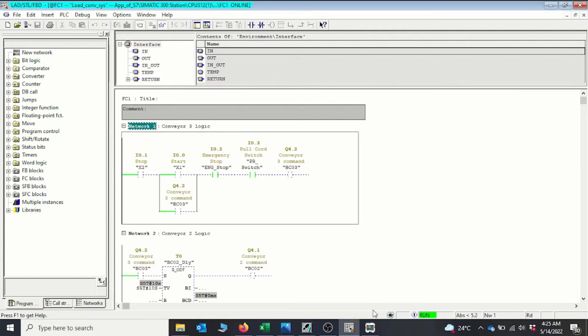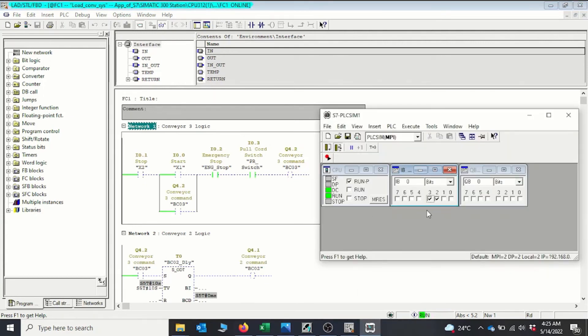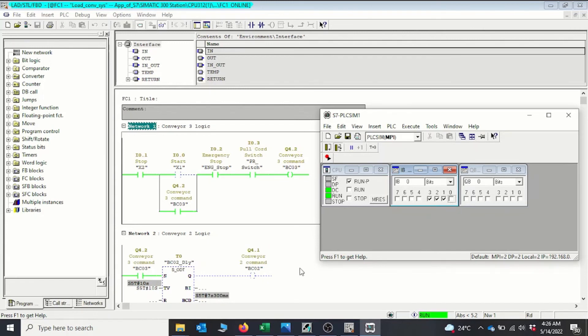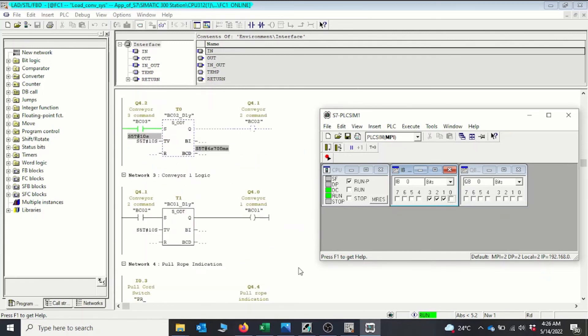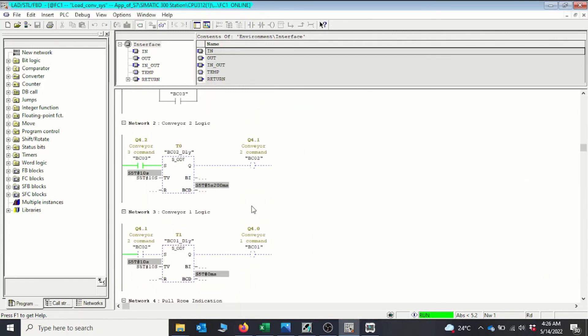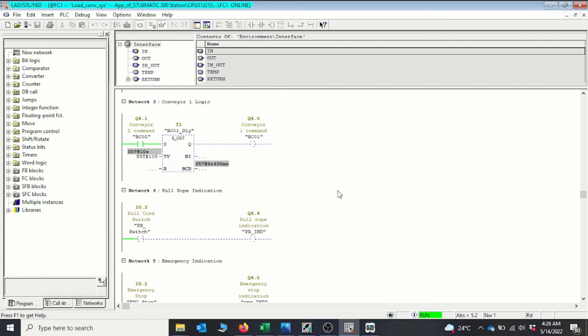To demonstrate starting the conveyors: the stop push button is also normally closed, so it needs to be ticked during simulation. It's closed. If I click on the start — which is a momentary switch — and stop, conveyor one starts and waits for the next conveyor. It counts down, then the second conveyor starts successfully. Then we wait for the third conveyor, and it also starts.